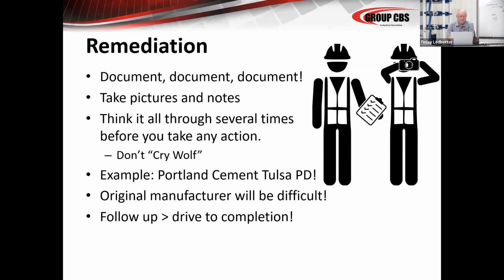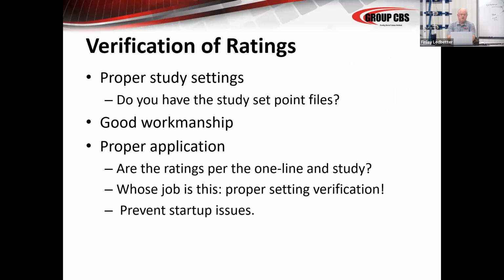Follow up. Missing components, parts of the system you haven't tested yet, things that still need to be done, failed tests that need to be redone, drive to completion, continue to work until you get everything followed up. It's very important that you have some verification of ratings. You should have a schedule of all the breaker sizes, make sure all the correct breaker sizes are in the correct power centers. I've seen them where they've installed the wrong power panels. And some of the ratings were incorrect. They were supposed to be 50 kA. They were 42 kA or 12 kA and supposed to have been 25 kA.